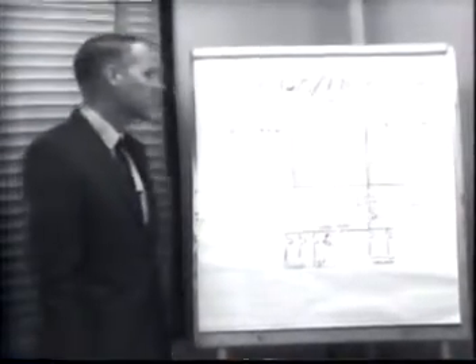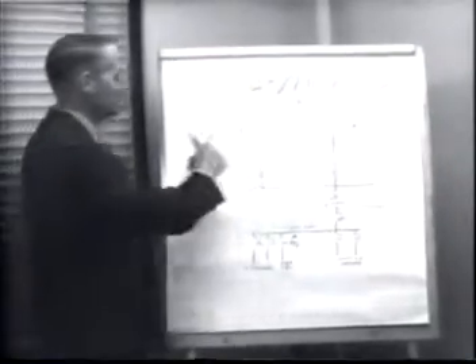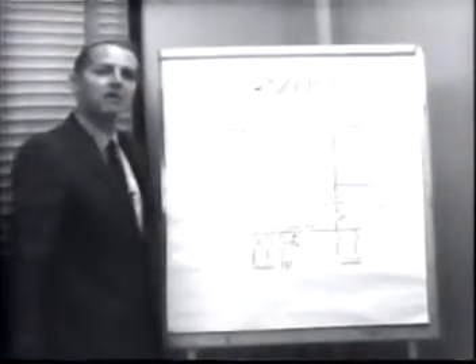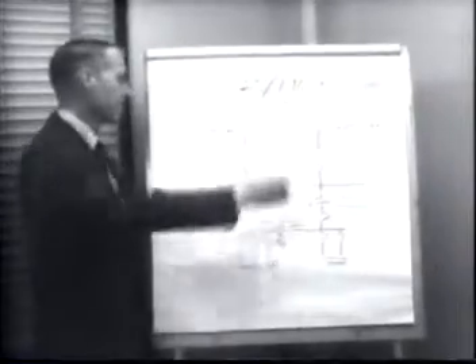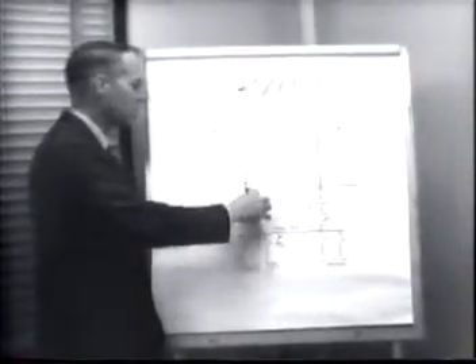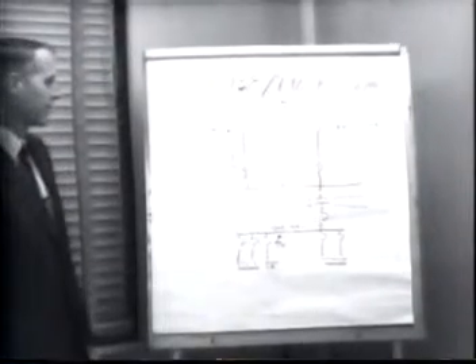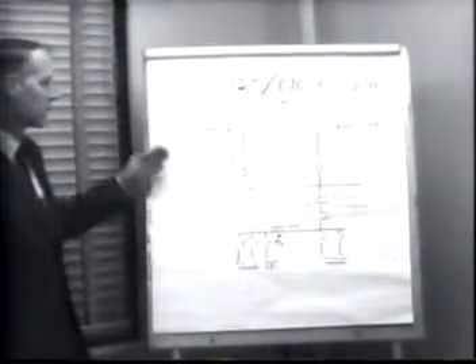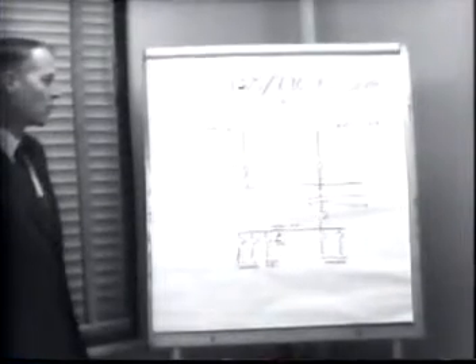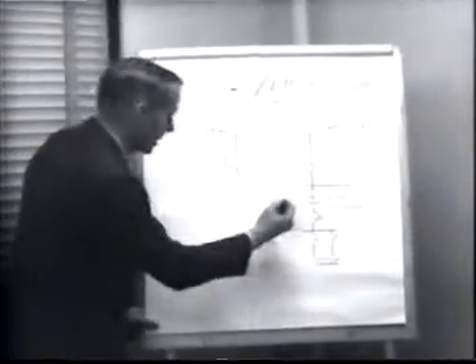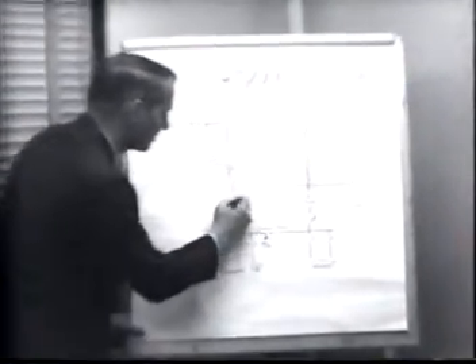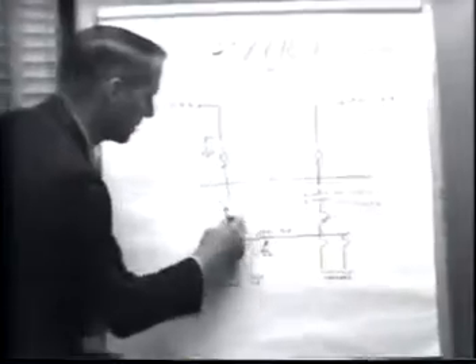As you can see, our typical pattern of construction, if we have a 69 kV line running past the substation site, would be to break into it, open it up, bring each line into the 69 kV substation structure, and then continue on. This allows us a two-way feed to this transformer. As the load increases in a specific area, we need more feeders out here. We can put in a second transformer here.